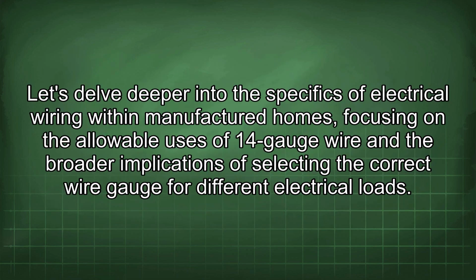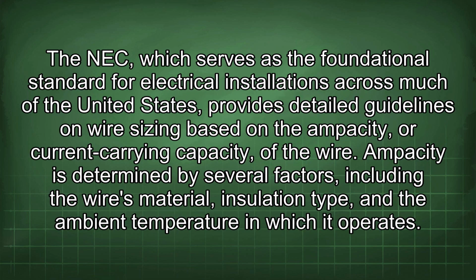Let's delve deeper into the specifics of electrical wiring within manufactured homes, focusing on the allowable uses of 14-gauge wire and the broader implications of selecting the correct wire gauge for different electrical loads. The NEC, which serves as the foundational standard for electrical installations across much of the United States, provides detailed guidelines on wire sizing based on the ampacity, or current carrying capacity, of the wire. Ampacity is determined by several factors, including the wire's material, insulation type, and the ambient temperature in which it operates.